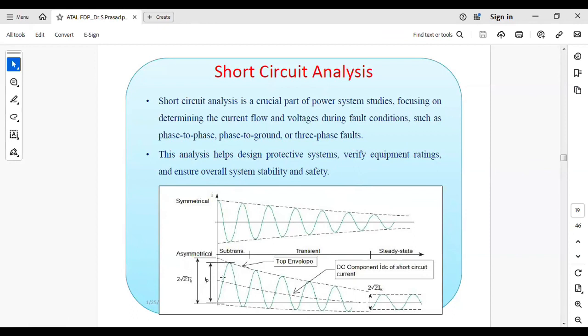What is the value of Ik double dash that we first calculate for different kinds of fault, like three-phase short circuit, line to ground, LG, double LG, LL. For each case, what is the Ik double dash, the symmetrical short circuiting current? Because based upon Ik double dash, the breaker rating will be decided.